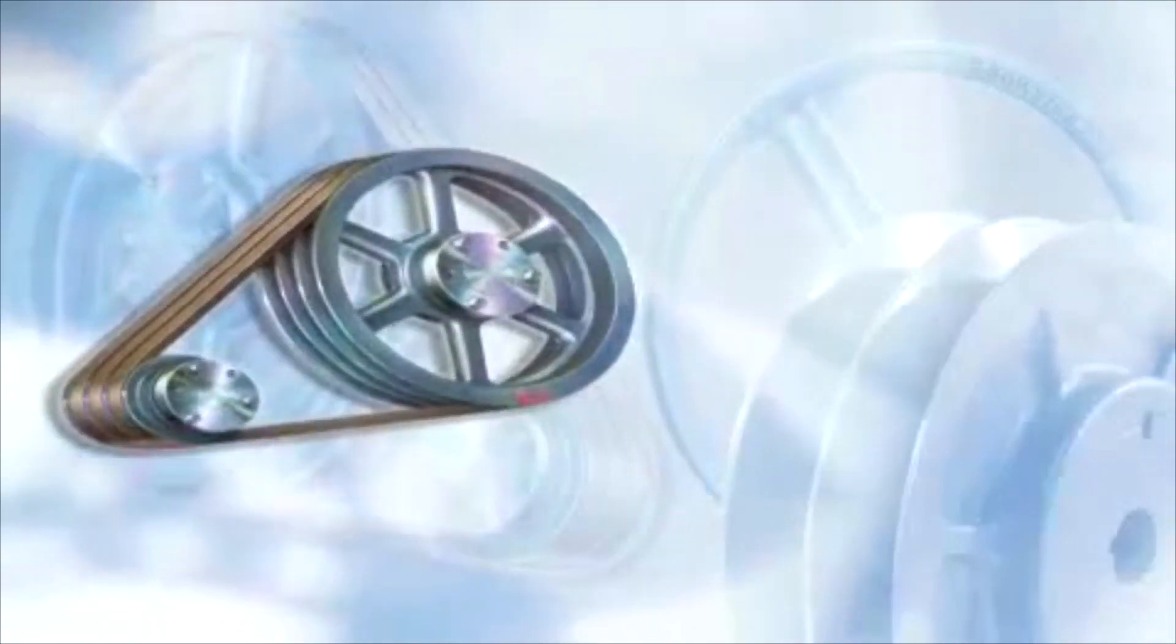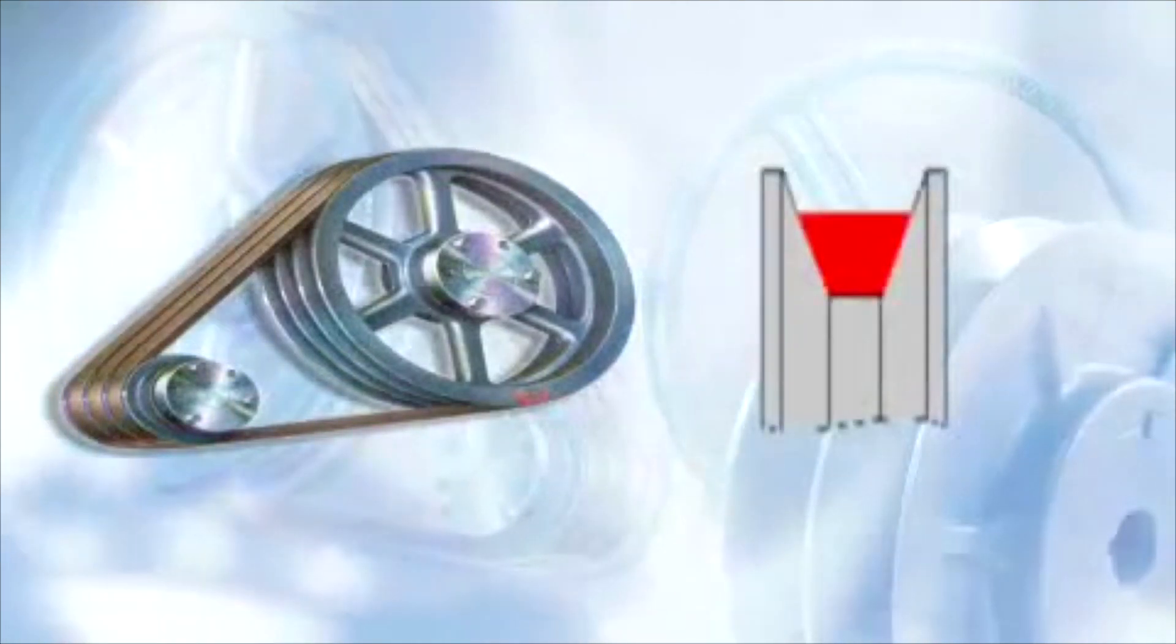To detect wear, look for the correct belt ride. The belt should never ride in the bottom of the groove.